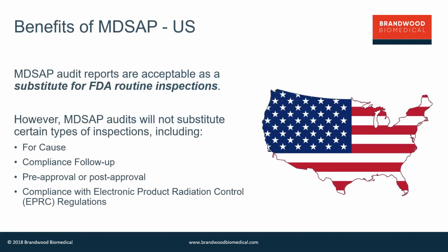PMDA. Going to the US, MDSAP audits are acceptable as the substitute for FDA routine inspections. So with the MDSAP audit, there's the expectation that you will not need an FDA audit at the time of your submission or during your routine inspection phase. Now, what it doesn't necessarily substitute for are, as we spoke about before, for-cause audits, anything that's related to compliance follow-up, things that require pre- and post-approval audits, and then those that are related to the electronic product radiation controls.